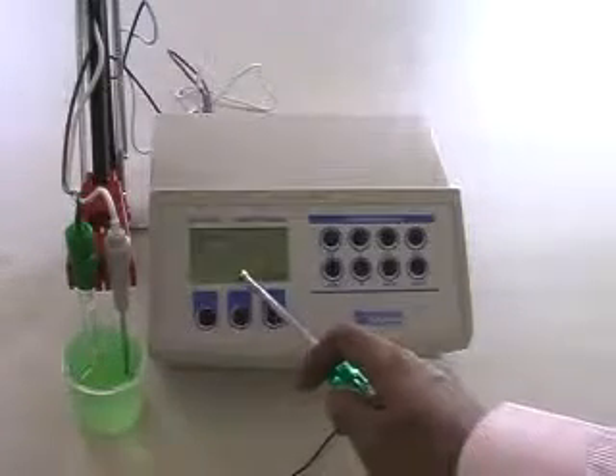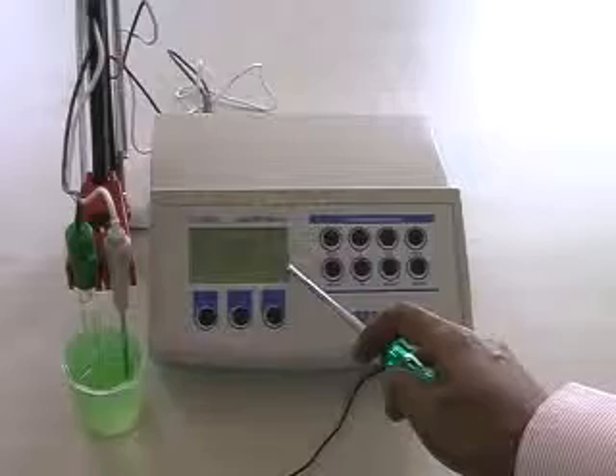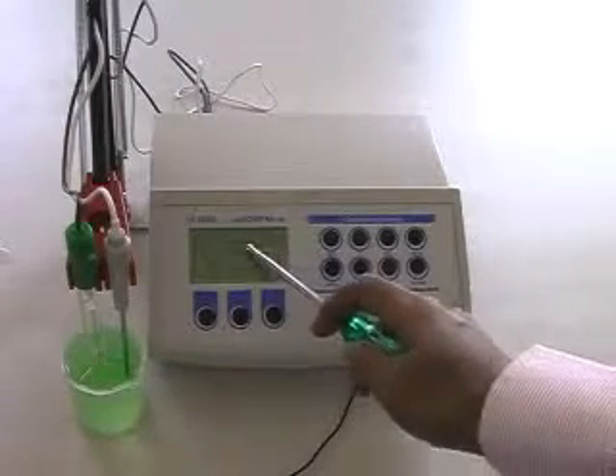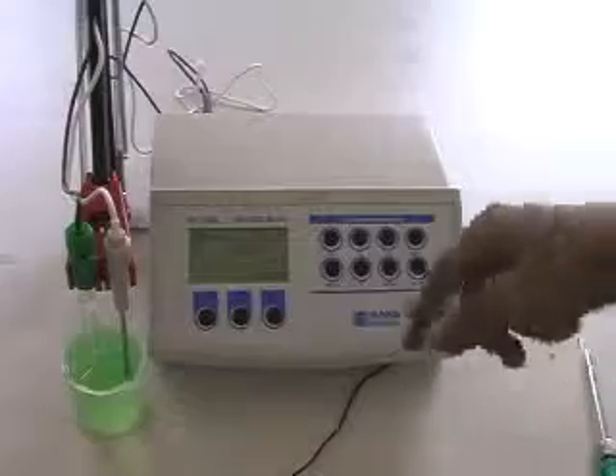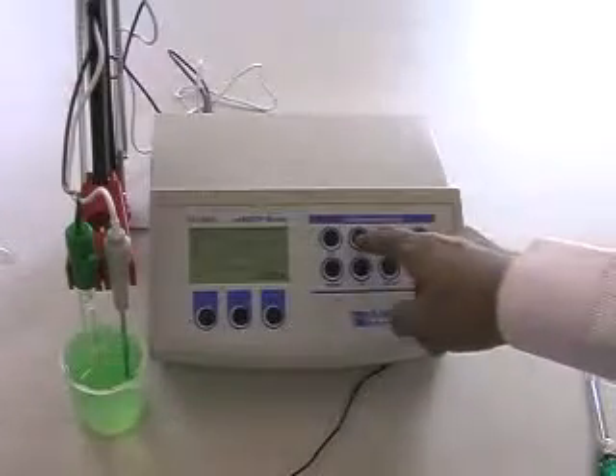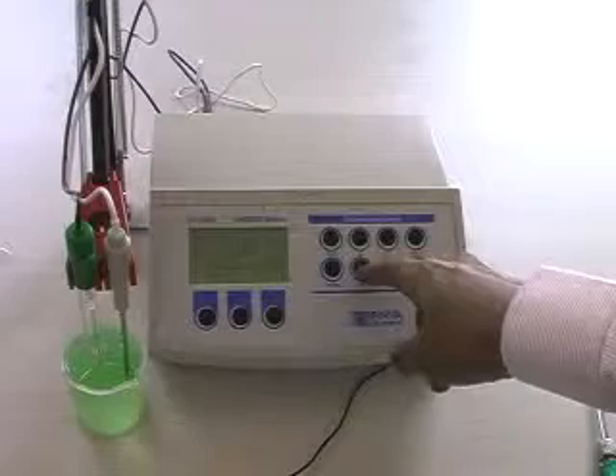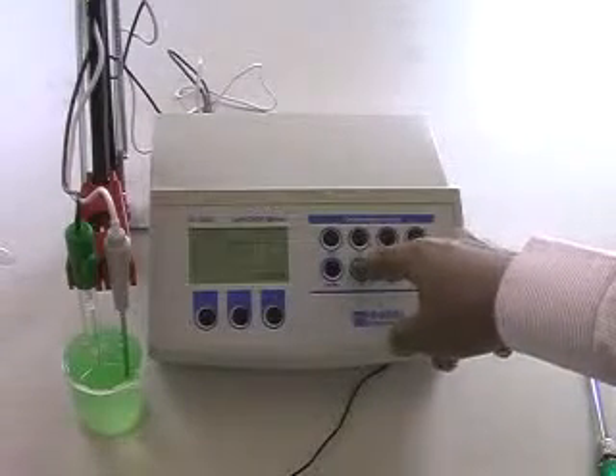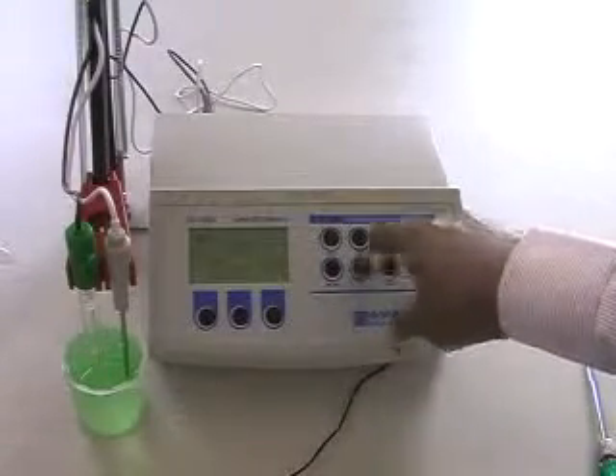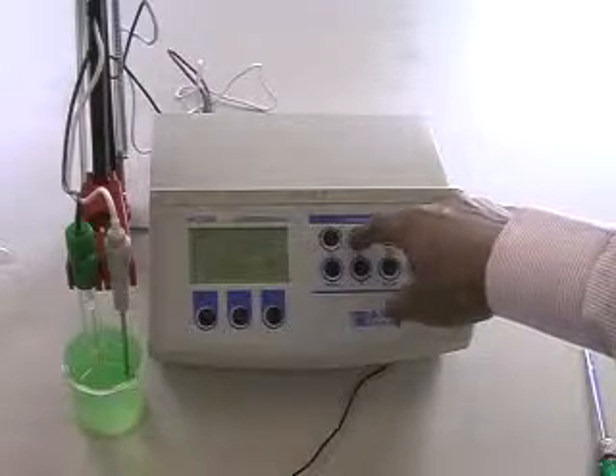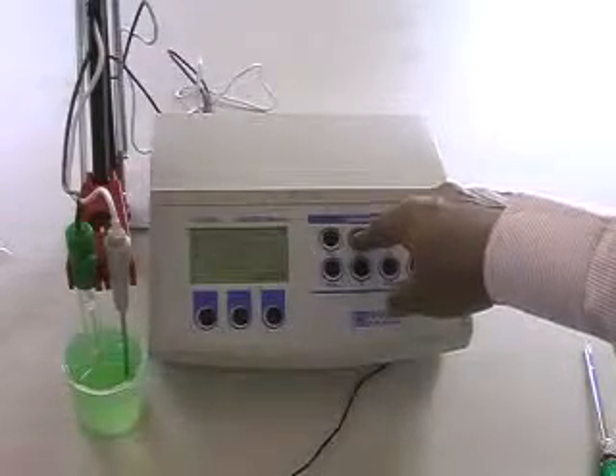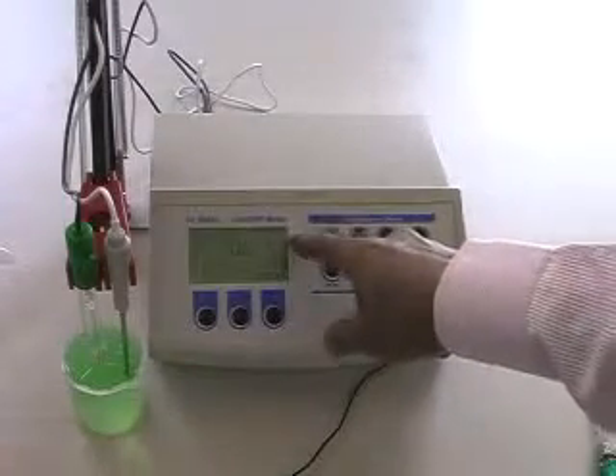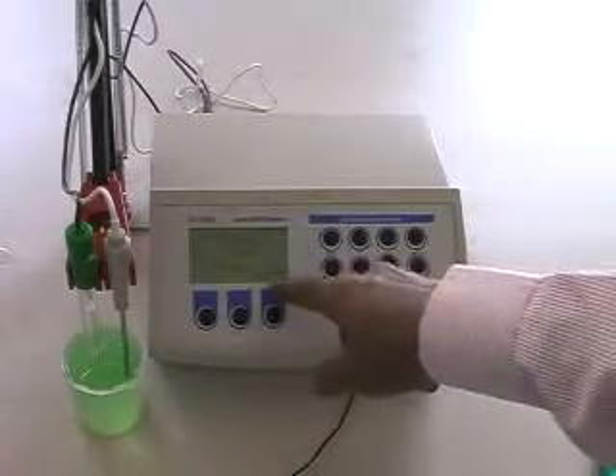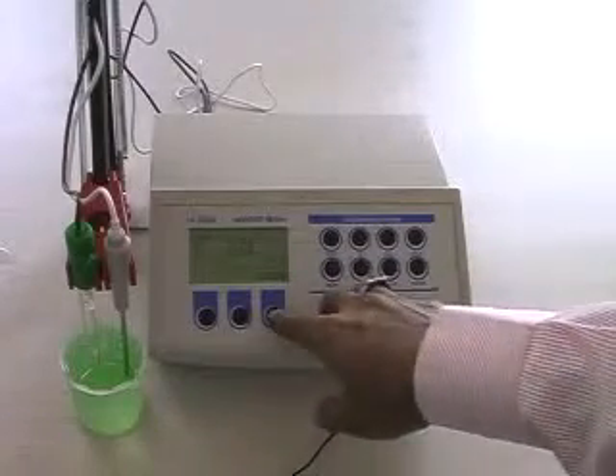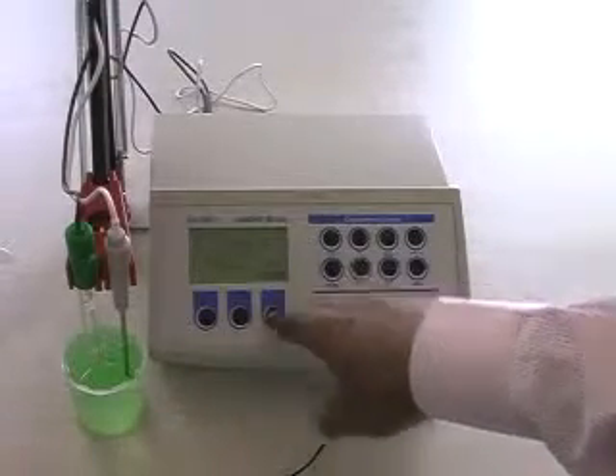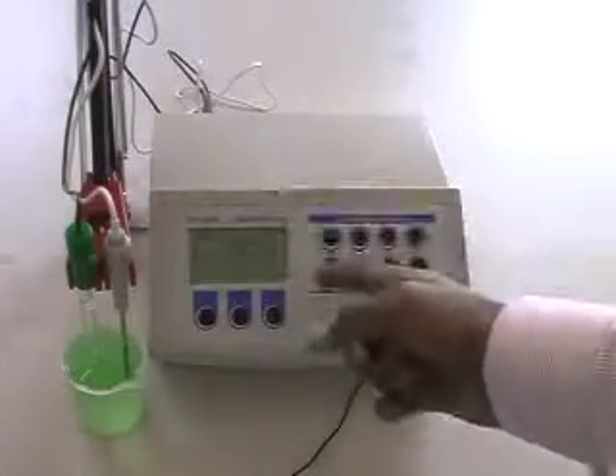Now the display is showing buffer 1, 7.01 pH value and temperature, and this is the current measurement value. If you want to calibrate your instrument for another buffer, you can select the other calibration solution like 6.86, 4.01 or 1.68. But today we are calibrating your instrument for 7.01. It will take some time to calibrate. After that, the instrument will display confirm. At that time, you have to just press this confirm button. This is a confirm. So it means that your instrument is calibrated for 7.01.